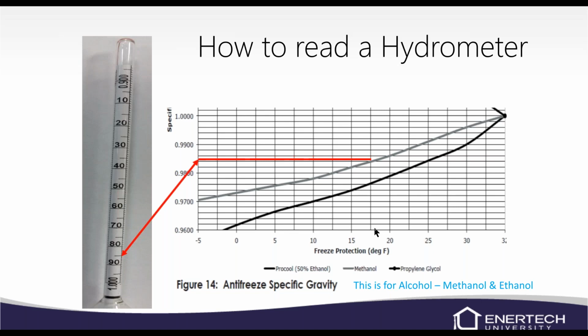This is an alcohol. Alcohol is either methanol or ethanol, and it's lighter than water, water being 1.0 on this chart. And you can't see it, but the propylene glycol would be on the top of the chart because it's heavier than water, so we would be at a number above 1. With methanol or ethanol, we're below 1 because we're lighter than water.